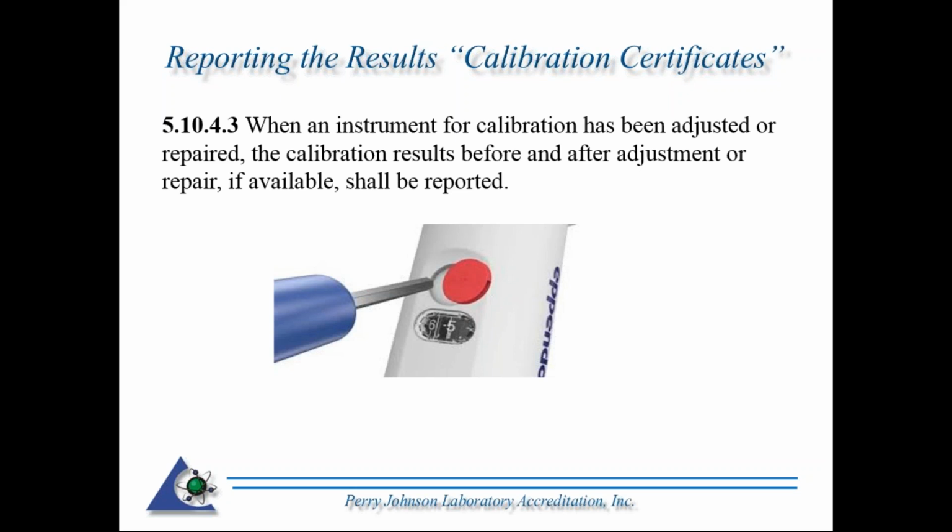So again, you may not be reporting uncertainty on the certificate. You still need to know what it is, and you still need to take it into account, of course, when you're saying something passes or fails, and I need to specify how that was taken into account.